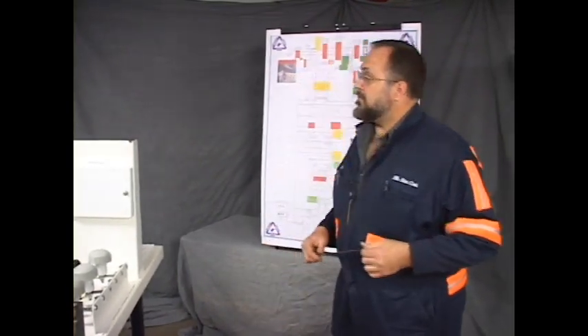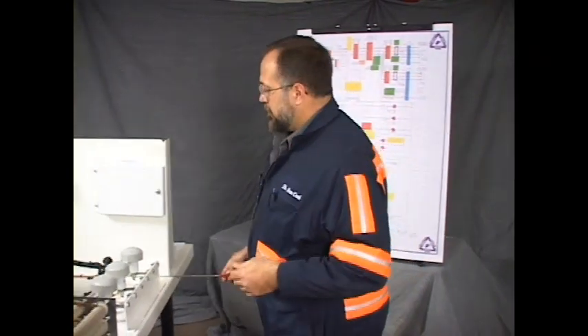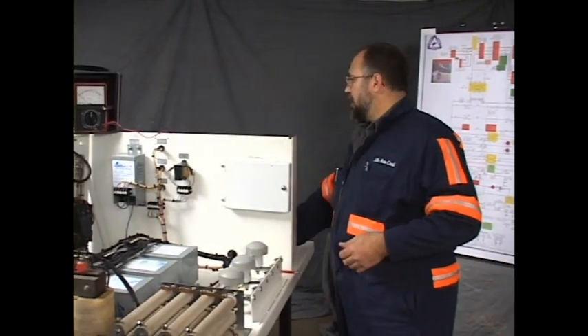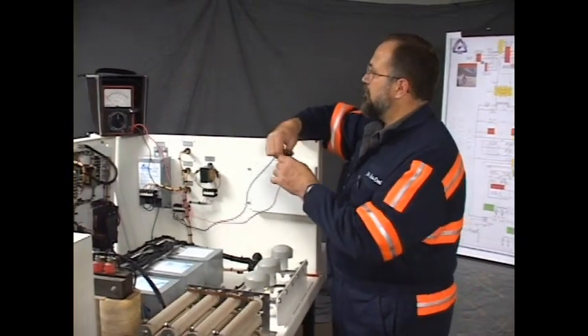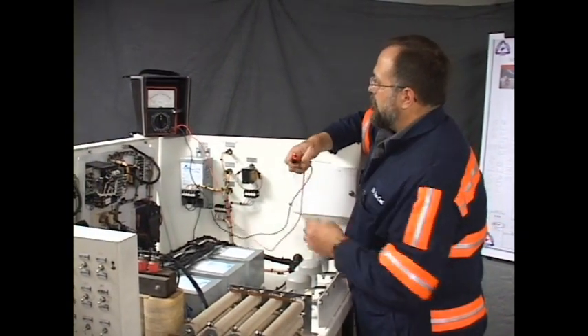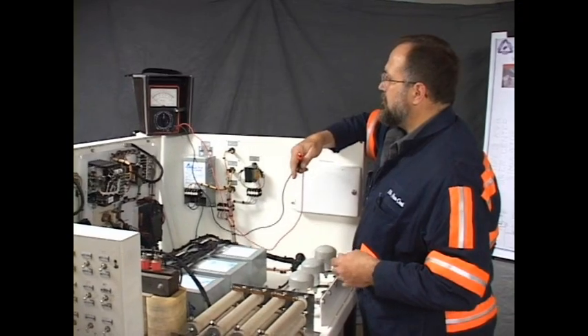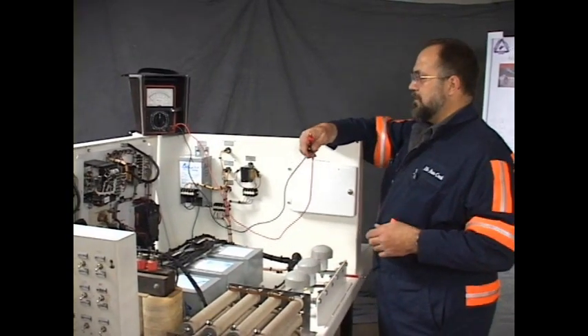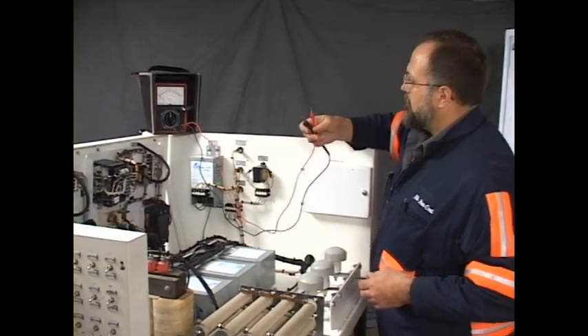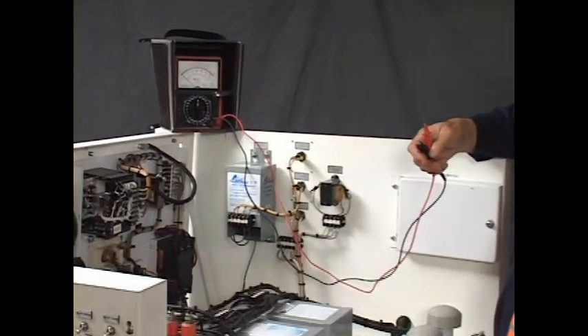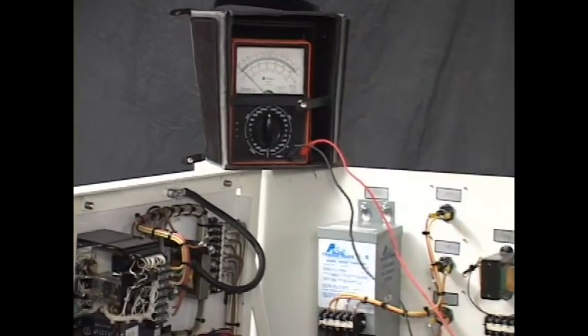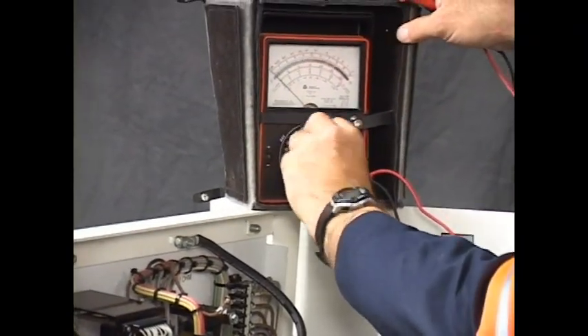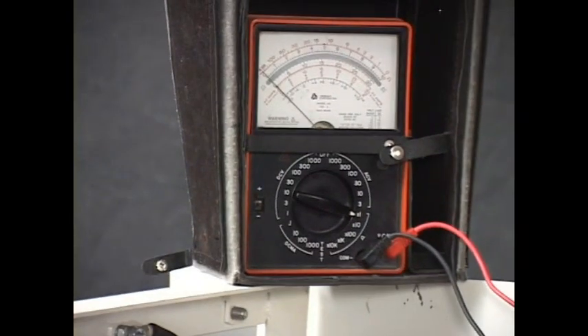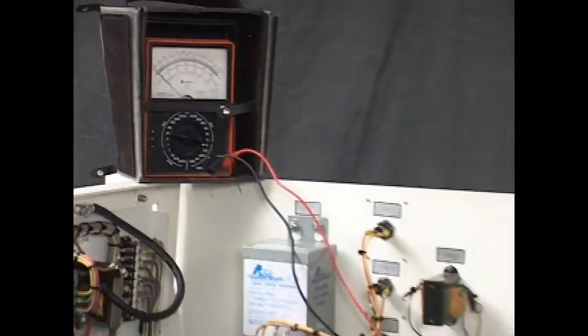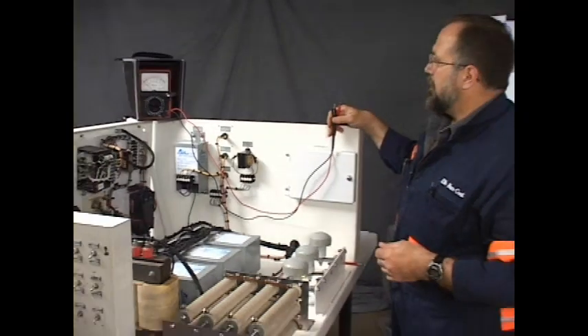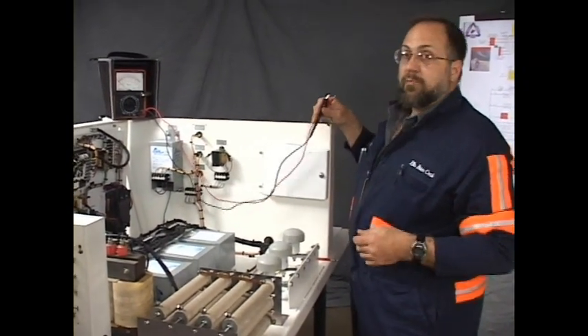So to start off with, we're going to use an instrument here to measure continuity. This is a fairly common brand. This is a Triplett Model 60 multimeter. It can check AC volts, DC volts, as well as continuity checks. It has two probes, and what we're going to be measuring here is continuity. So I'm going to set this to read resistance times 1. The X1, X10, X100, X1K, X10K, those are actual multipliers.